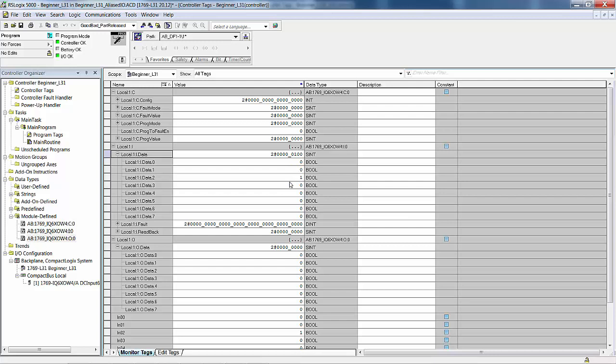So I'm going down and turn these inputs on to show you that in the program mode, then this is with the Logix engine, not with SLC 500 and MicroLogix. Inputs are updated regardless of the mode of the controller. Now I'm going to put it back in the run mode, remote run mode.